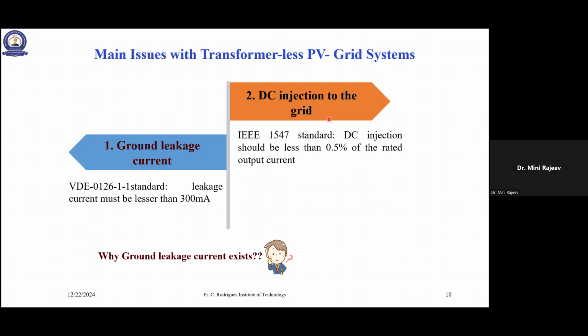Now, this creates many problems, like it will saturate the distribution transformers and it will increase the losses in the system. The IEEE 1547 standard says that DC injection should be less than 0.5% of the rated output current. IEC says that it should be less than 1% of the rated output current. But there is a limitation according to the standard. So right now we will be concentrating on the ground leakage current.